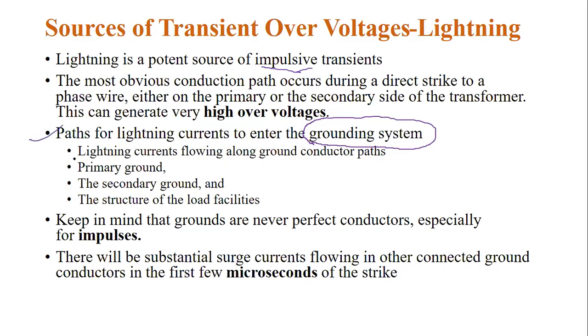Okay, now see this path. The first path is the lightning currents flowing along with ground conductor paths. That's the first one. What is the second one? The primary ground of the transformer. And the third one? Secondary ground of the transformer. Then the fourth one: the structure of the load facilities. You know which type of load we are connected to—based on that, the transient also varies. Now keep this in mind, remember these points: grounds are never perfect conductors to clear these transients, especially impulses.